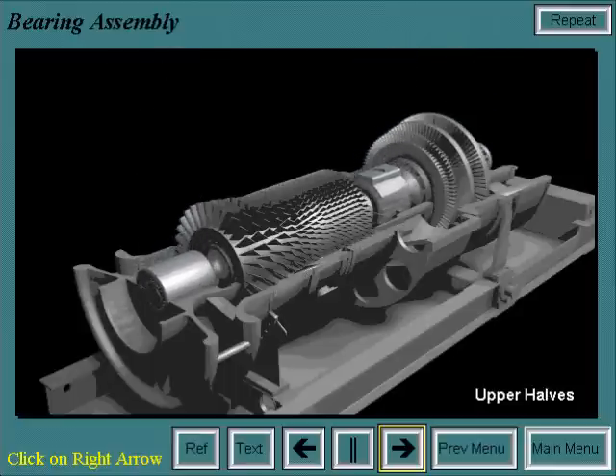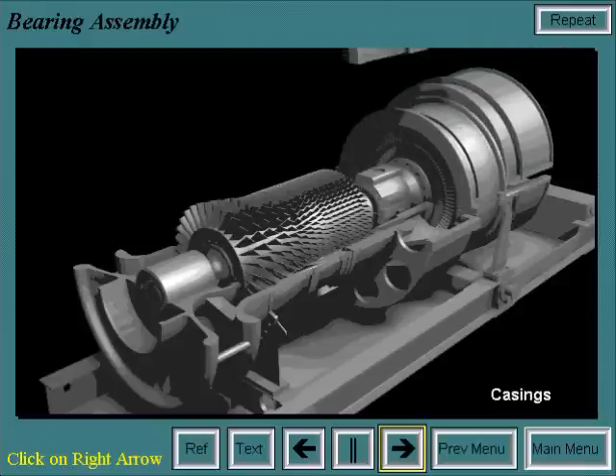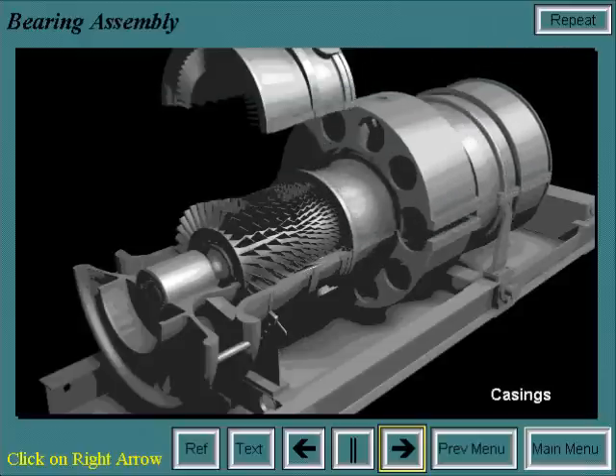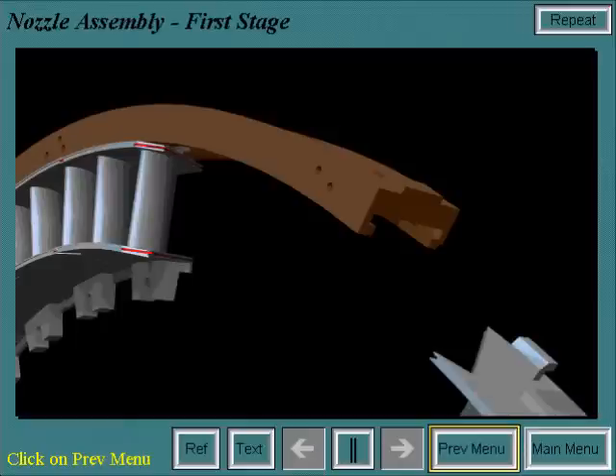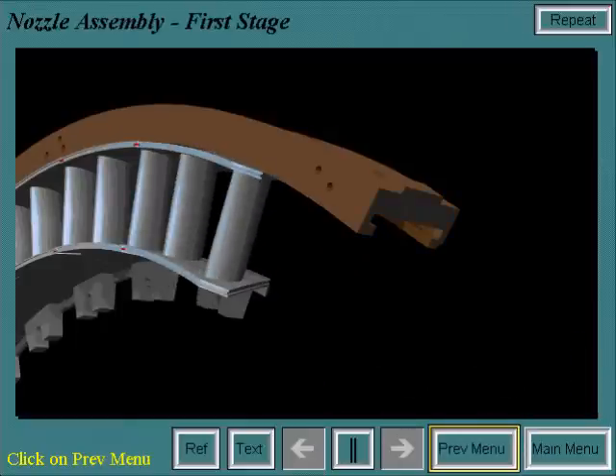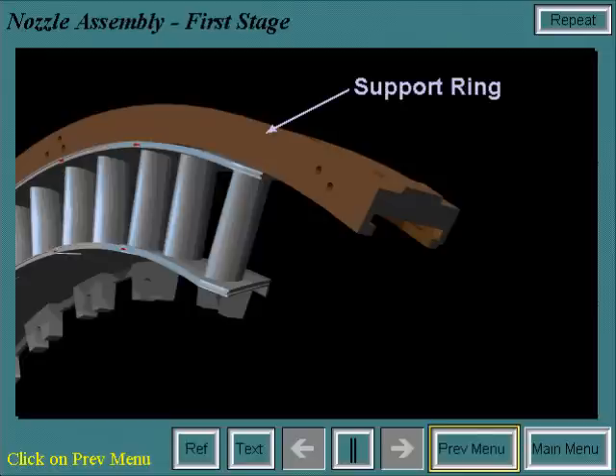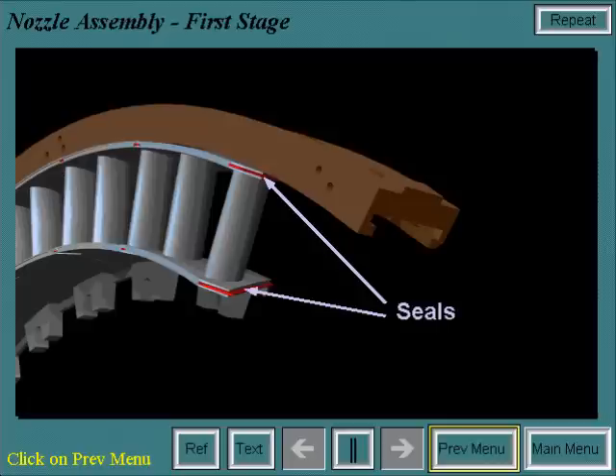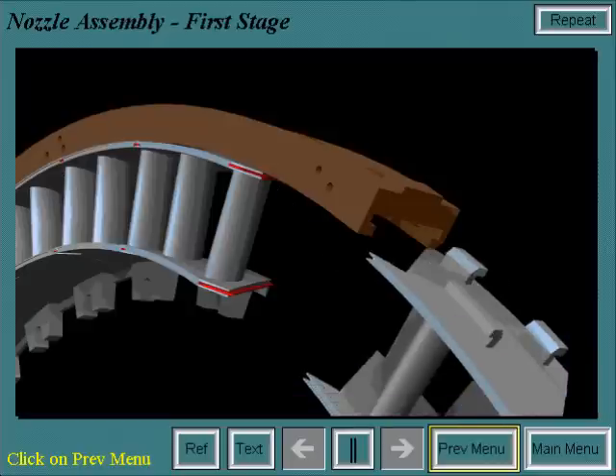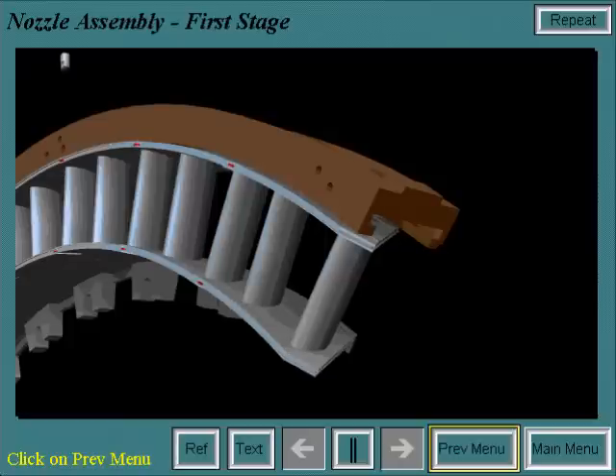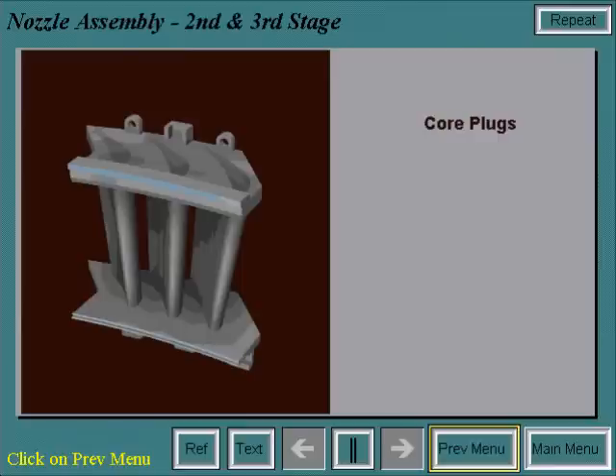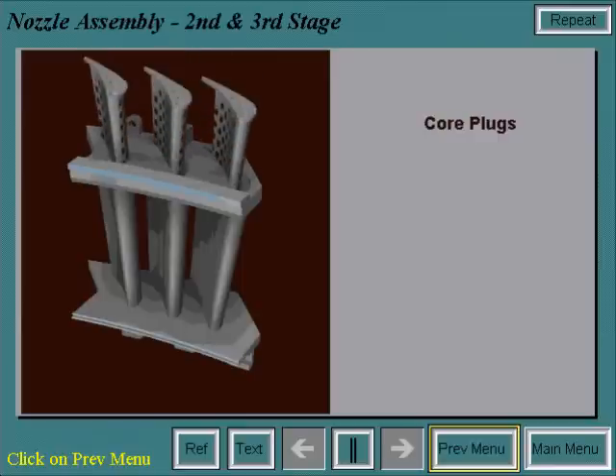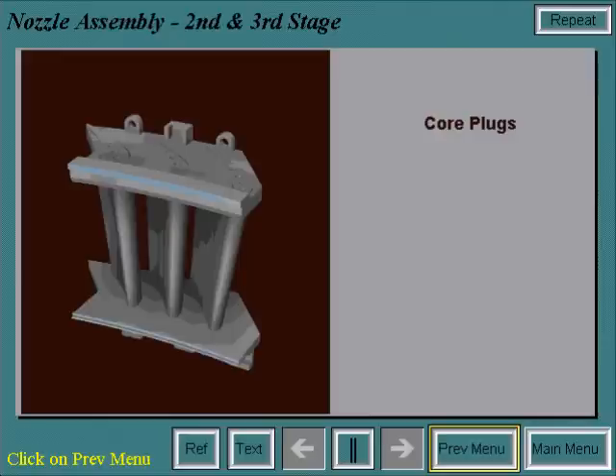The final step is the installation of the rotor and the upper halves of the bearing housings and casings. To assemble the first stage nozzle, the nozzle segments are installed into the support ring. Seals are installed to minimize gas leakage. Alignment pins are then installed to radially align the segments in the ring. To assemble the second stage nozzle, first a core plug is installed in the investment cast piece to allow for even cooling down the center of the bore of the nozzle segment.